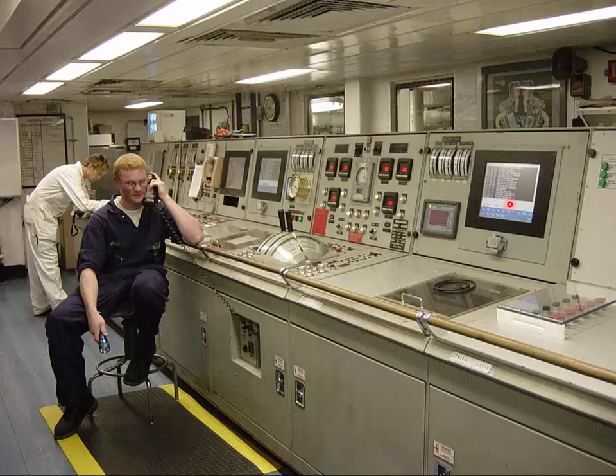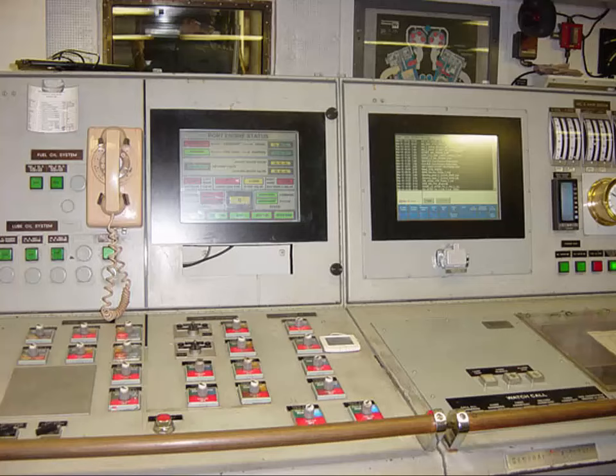Now, this has a menu system. A distributed control system typically has menus that you can look at for each of the different systems, and you're very familiar with this. So the majority of your information on modern ships now is coming through these HMI units. And most of your control, there are ships that you specifically go through the computer systems for controlling the vessel. And it has to be that way because this engine room has to be able to operate on its own when humans are not in attendance.